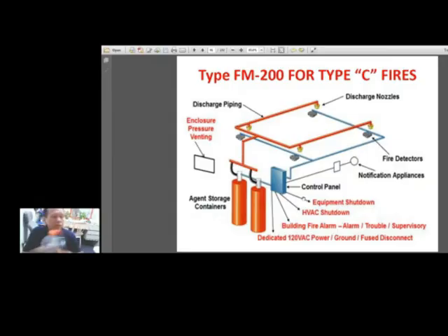Okay, so here you have these two cylinders as the agent storage containers, these ones. And you have their piping here, the orange piping, and you would have the nozzles here. 4 discharge nozzles, 1, 2, 3, and 4, equally spaced on top of the room that should be protected. You will notice that there are fire detectors. This one, this one, this one, and this one.